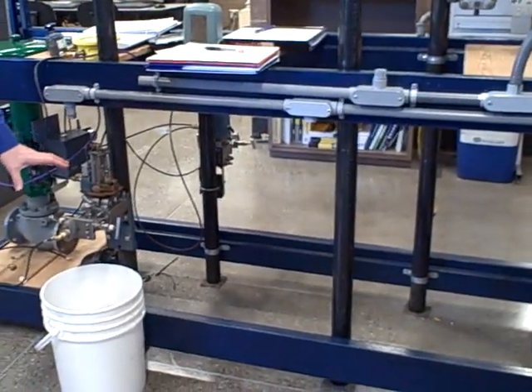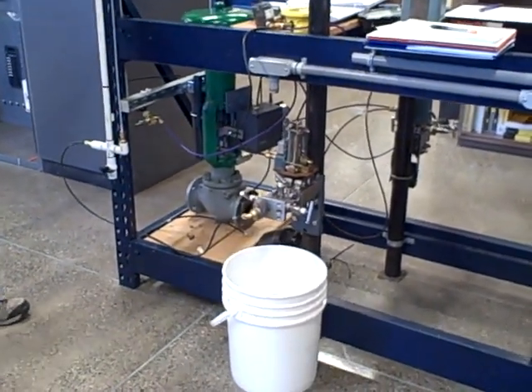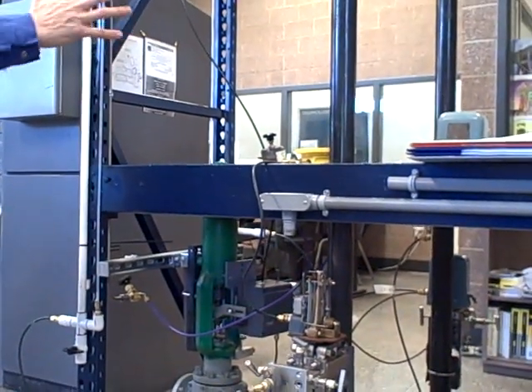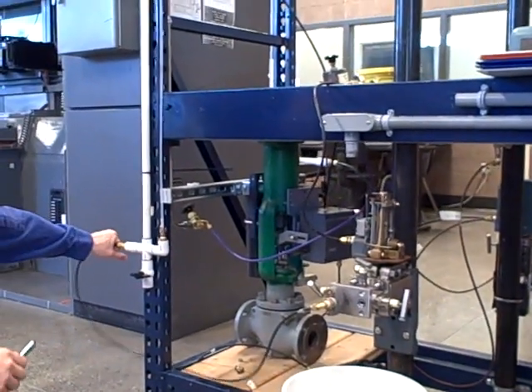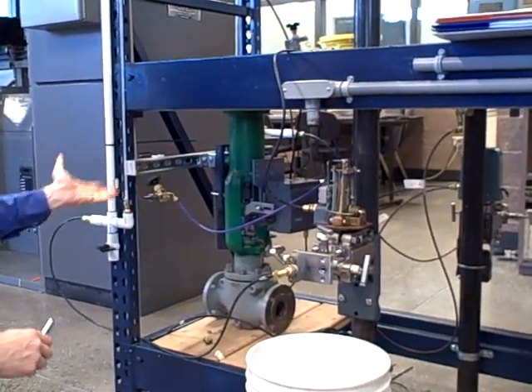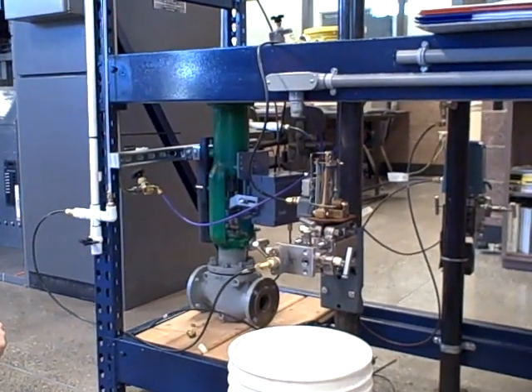We've got a Foxboro Model 13A transmitter. We're using it to measure the level of liquid inside this process vessel. Now this vessel is nothing more than a PVC tube, but it's representing what could be a huge tank. This transmitter is going to measure the height of water inside this tank. The way we do that is we hook up an impulse line between the bottom of the tank and the transmitter, going to the high side of the transmitter, so the more water level we have, the more pressure we'll have, and this transmitter outputs a 3 to 15 PSI pneumatic signal representing that water level.